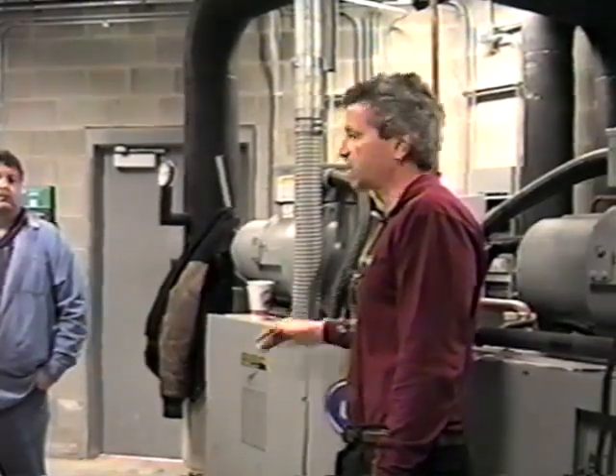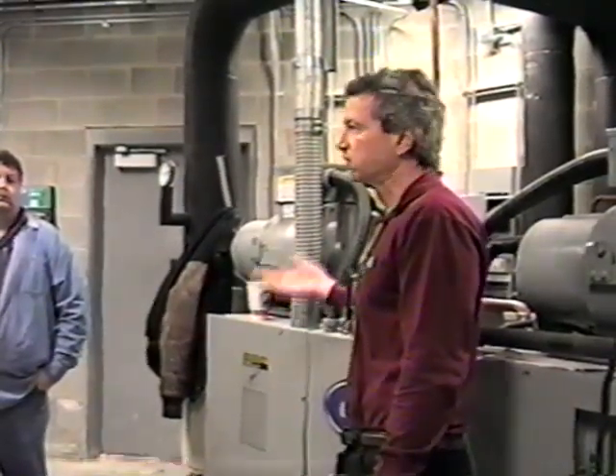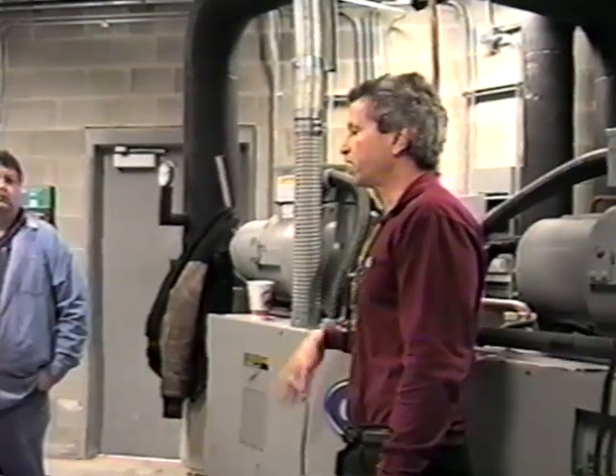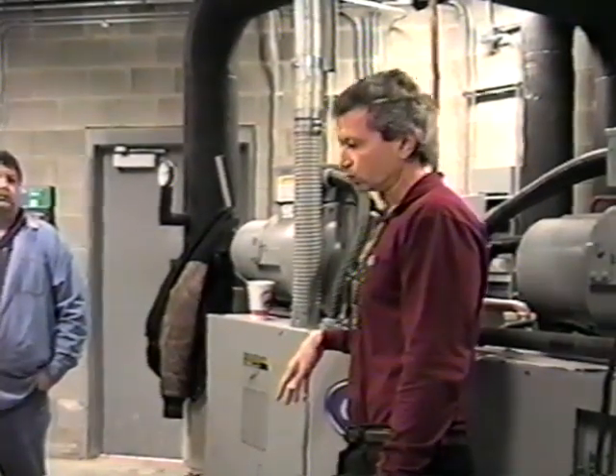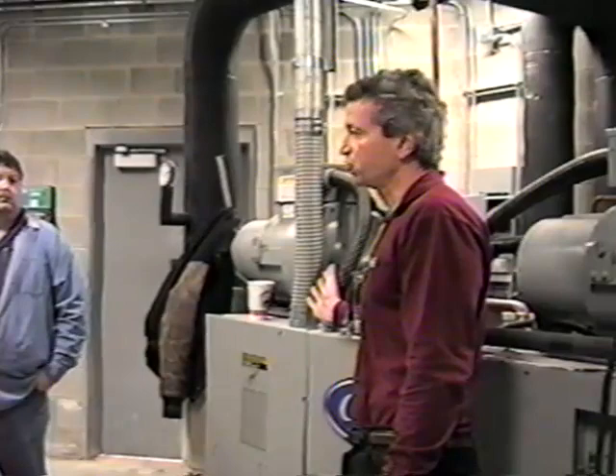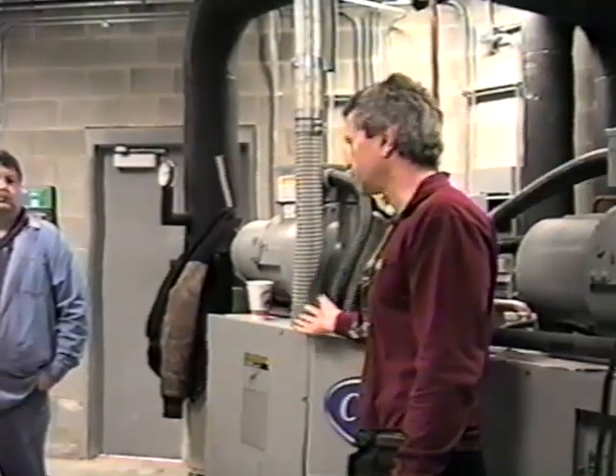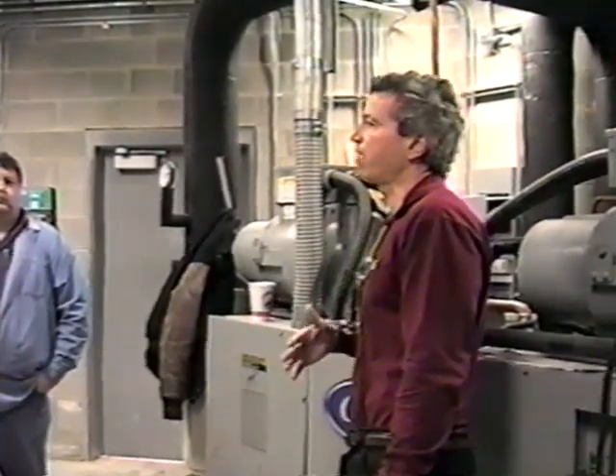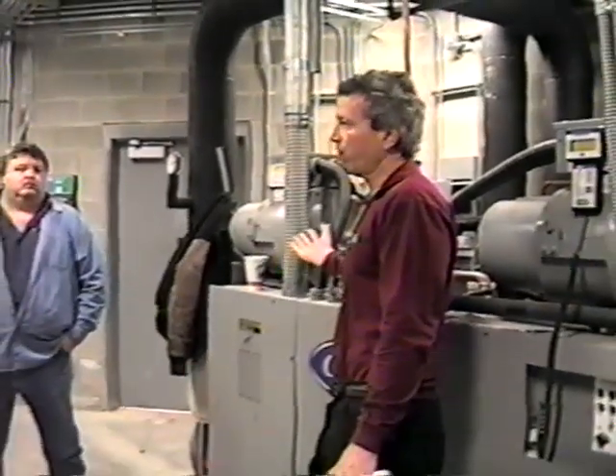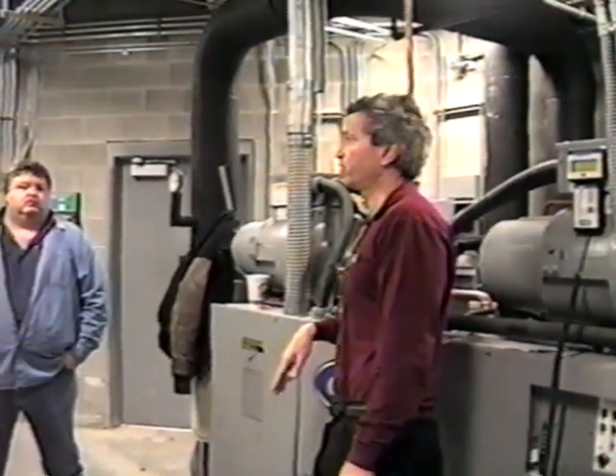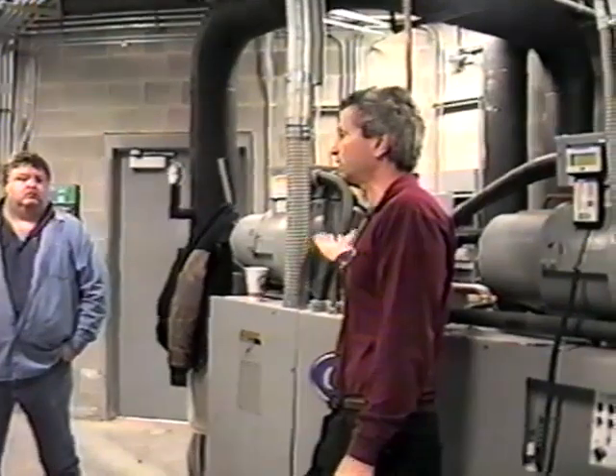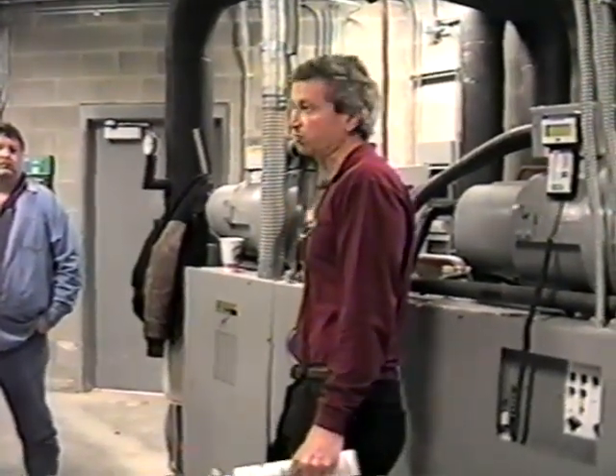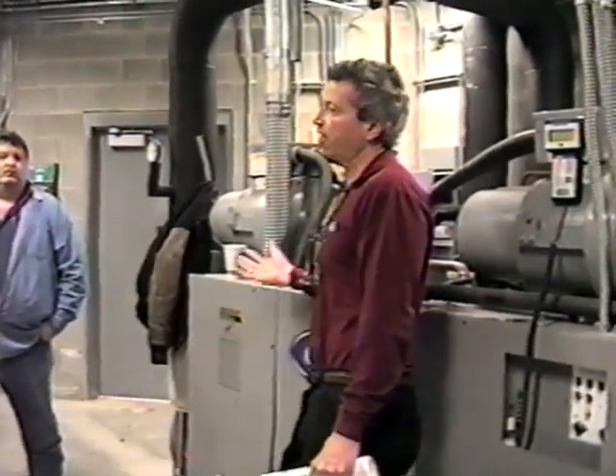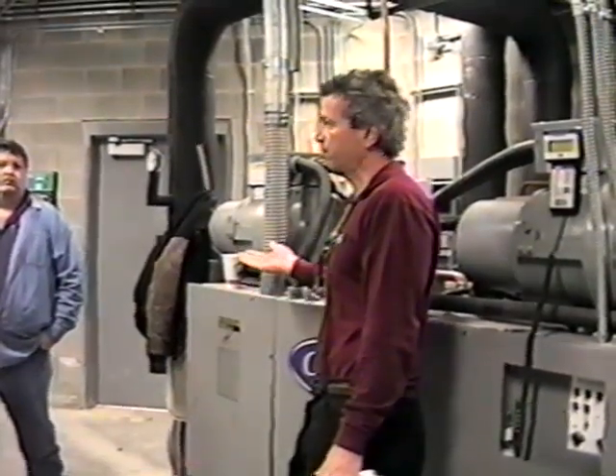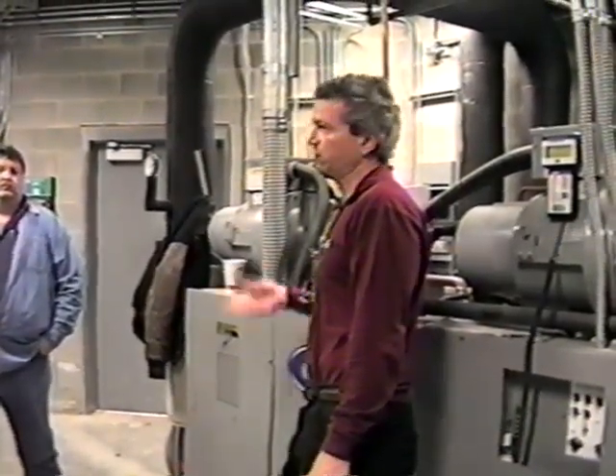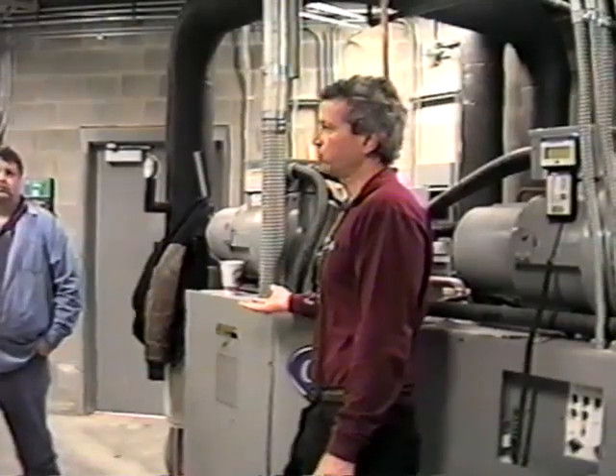So, having said that, again, the initial startup was done about a month ago, or a little less than that. Where we came in, we go through the machine, do all the pre-startup checks, do all the initial programming, and then get the machine up and running per design specifications that basically were what this machine was sold for. In your case, it's designed to do 17.5-degree return brine and 15-degree supply brine for the ice cream.